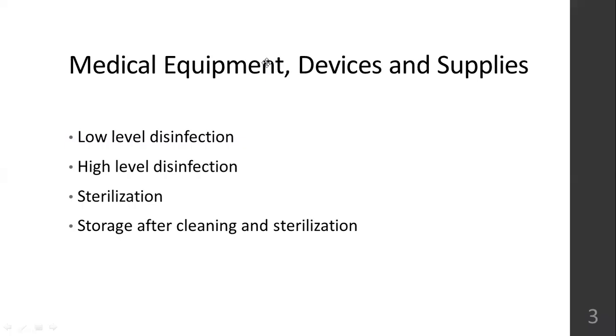When you are storing all these items after the processing is done, it should be in a clean, dry, dust-free, well ventilated area. Temperature should be between 18 to 24 degrees Celsius, and relative humidity should be around 35 to 70 percent. Too much humidity should not be there, because microbes will grow inside the sterilized instruments. Closed cabinets are preferred, not open shelves. If possible, go for closed cabinets.